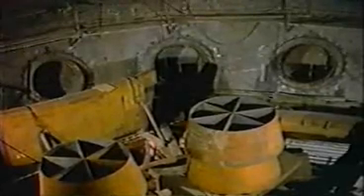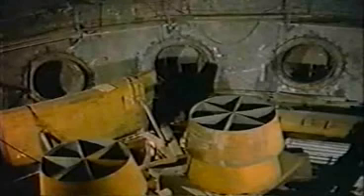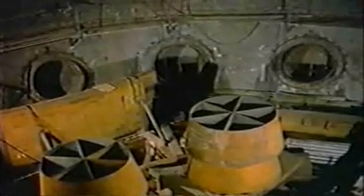Perhaps the most arduous task within the reactor vessels was the establishment of clean conditions. The interior walls had to be flame cleaned and wire brushed to remove all dirt, scale and foreign matter. Such incompatible materials have an adverse effect on the neutron absorption and hence reactor power. The inside of the vessel and all equipment used were coated with a colloidal graphite compound, and the cleanliness achieved was the equivalent of a hospital surgical room.